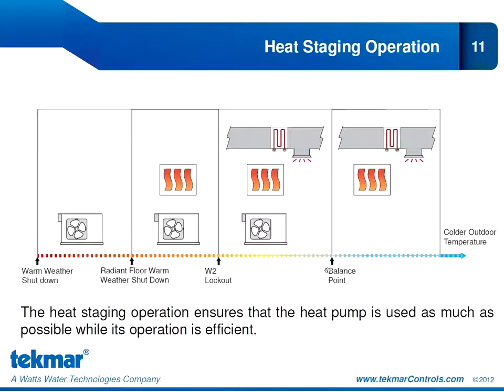If the outdoor temperature continues to drop, we see another new setting called the balance point. And this is particular to air source heat pumps only. We will go over this later in the webinar, but what this setting does is it prevents air source heat pumps from operating inefficiently. So when the outdoor temperature reaches a certain point, the air source heat pump does not provide any efficiency advantage. So we're not going to bring that on. We are going to instead enable our radiant floor as a first stage of heat and the electric strip backup as a second stage of heat. This heat staging operation ensures that the heat pump is used as much as possible while its operation is efficient, always maintaining absolute comfort for the homeowner.